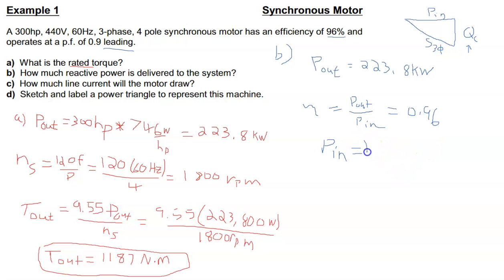And so power in then, power out divided by efficiency. And so remember, power in is bigger than power out. Just think about that when you're doing this calculation, because you don't want to do it backwards. So 223.8 kilowatts divided by 0.96. And so the real power at the input then becomes 233,125 watts, and I didn't bother to round it yet.